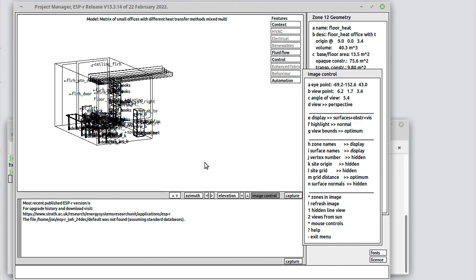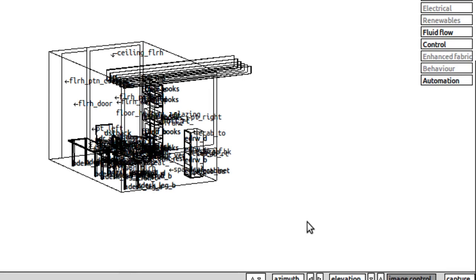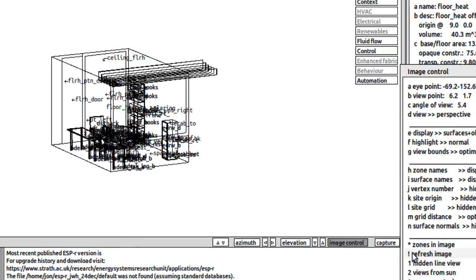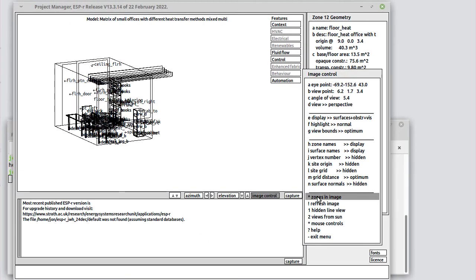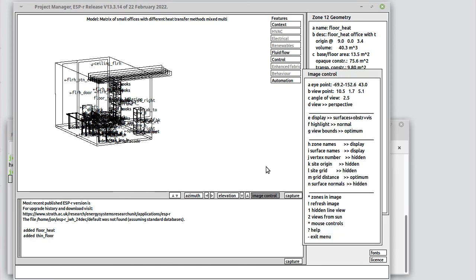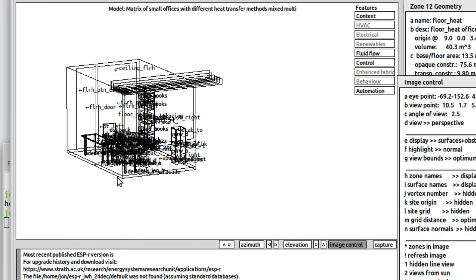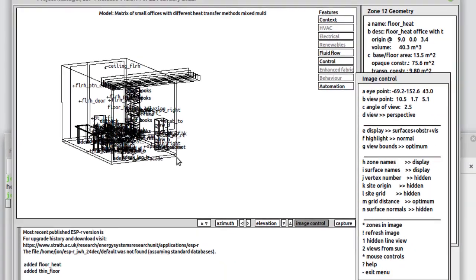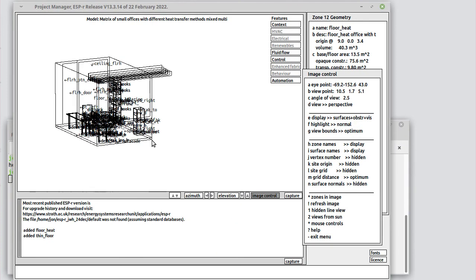This is a small office with furniture, fittings inside, shading on the outside. It's essentially identical to all of the other zones. But if we look at it with the thin floor, essentially we have a thin zone attached to the bottom of the zone where we're going to inject heat. We use a high heat transfer coefficient to ensure that heat is transferred into the structure above the screed and heats up the floor surfaces.